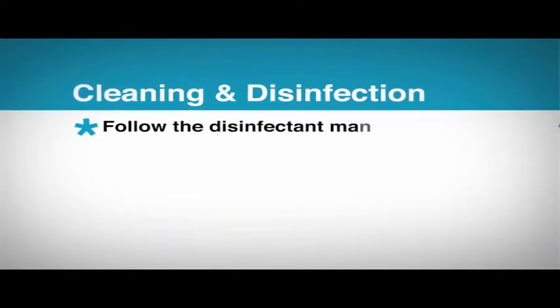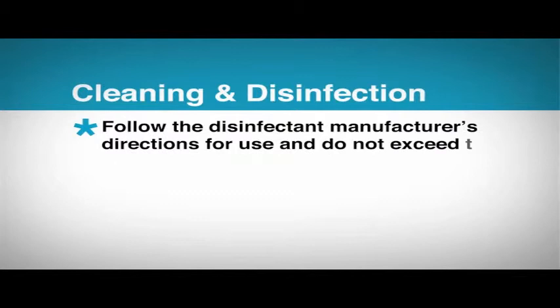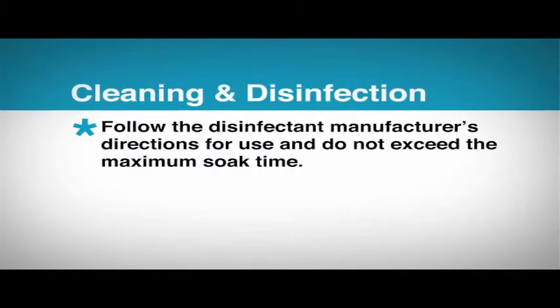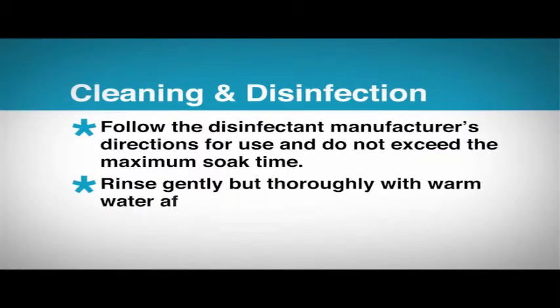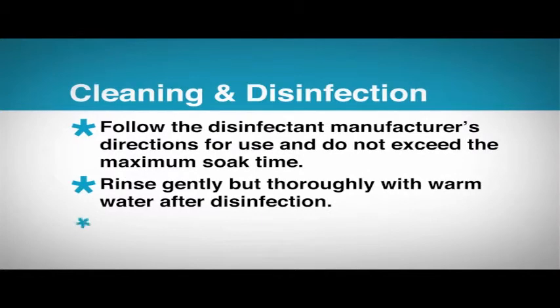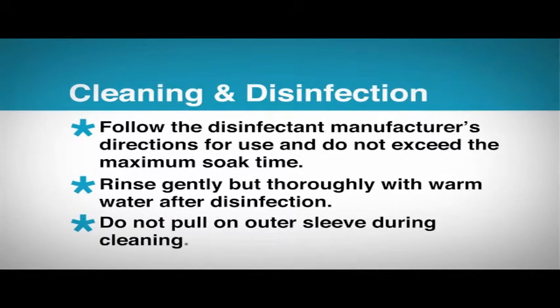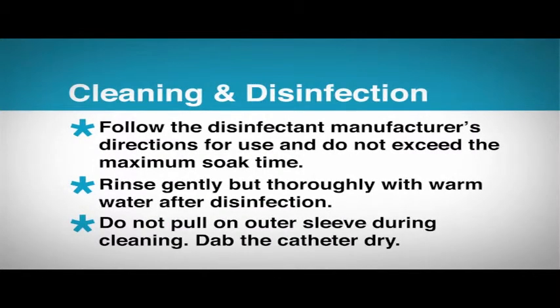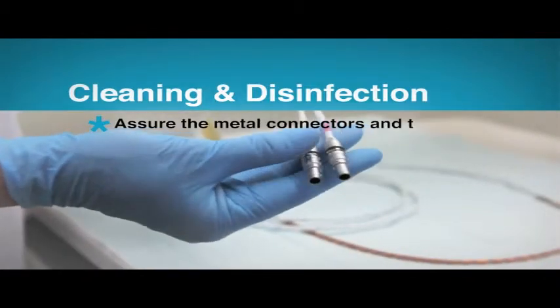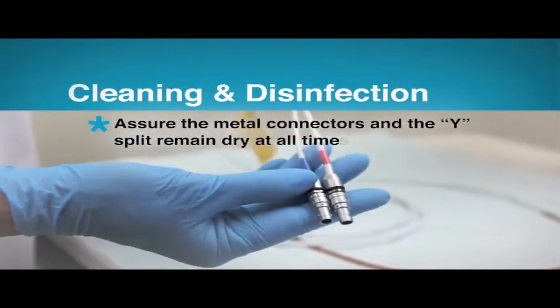Follow the disinfectant manufacturer's directions for use and do not exceed the maximum soak time. Rinse gently but thoroughly with warm water after disinfection. Do not pull on outer sleeve during cleaning. Dab the catheter dry. Assure the metal connectors and the Y-split remain dry at all times.